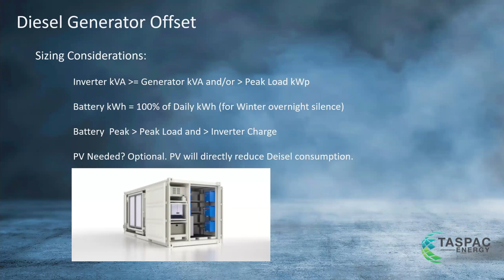Here's a bit of a case study from a customer of ours who installed this a couple of years ago, on Great Mercury Island - that was the end user. The generator requirement was reduced to 16% from 100%. They gave us the wrong daily consumption initially, using grow watts, and couldn't handle the generator - the grow watts were reporting 36 kilowatt hours per day. When we put our system in and turned it on, it was actually using 80 kilowatt hours a day. So it's working really, really hard, but it's working well.